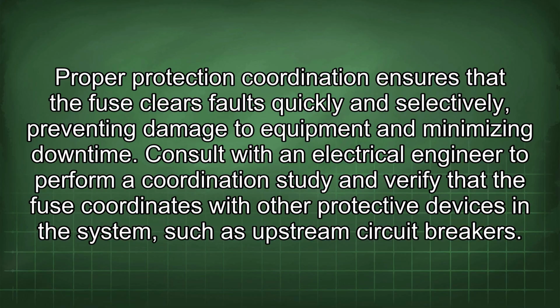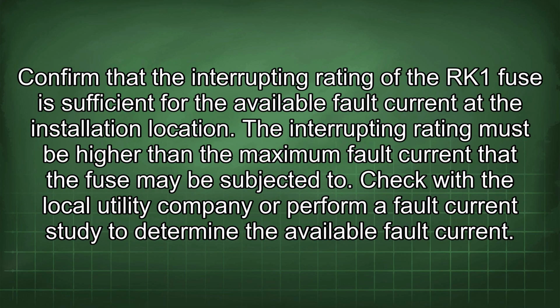Consult with an electrical engineer to perform a coordination study and verify that the fuse coordinates with other protective devices in the system, such as upstream circuit breakers. Confirm that the interrupting rating of the RK1 fuse is sufficient for the available fault current at the installation location. The interrupting rating must be higher than the maximum fault current that the fuse may be subjected to. Check with the local utility company or perform a fault current study to determine the available fault current.